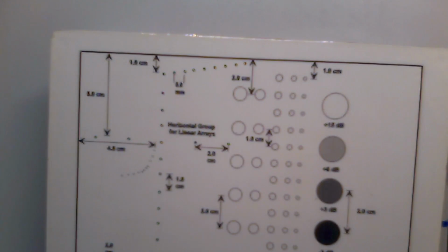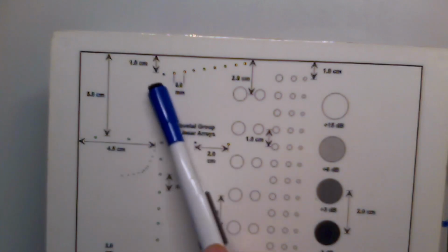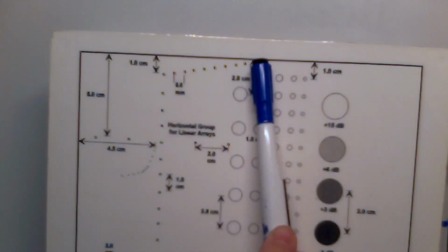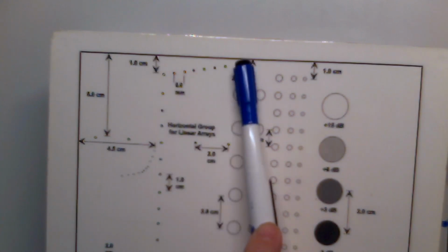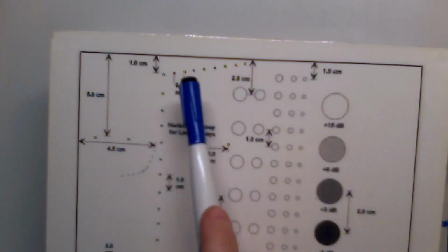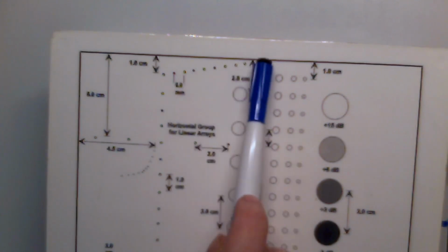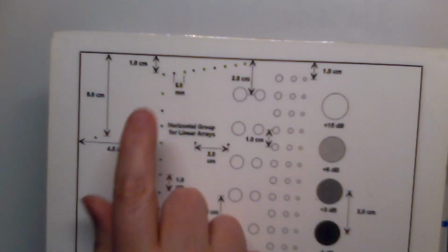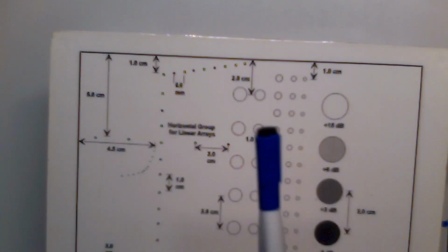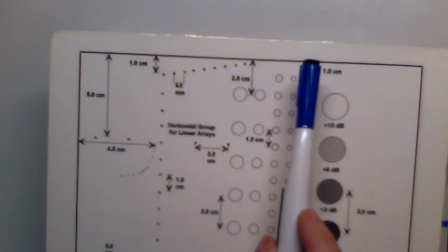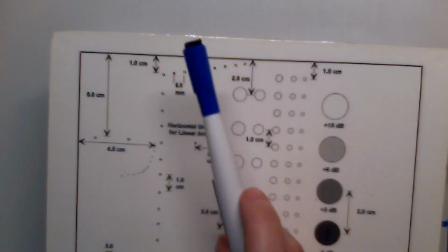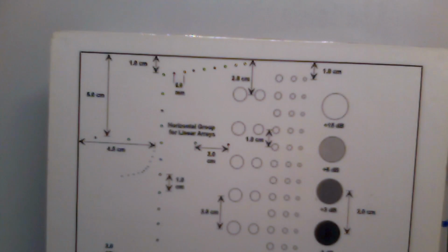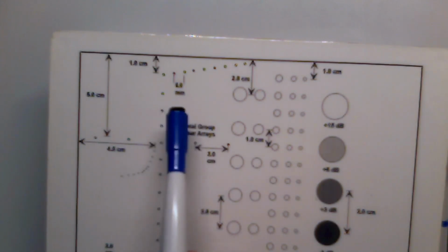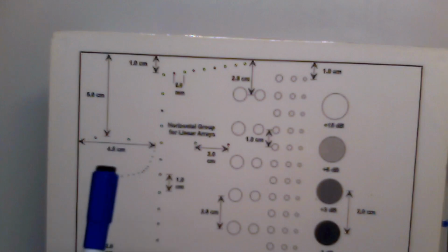Again, we are looking for little pins that are up near the first few centimeters of the phantom. So we're looking at these pins right here. Again, there are 9 displayed here. We want to see when our first one comes in. We can also check the accuracy of the machine in that very near field. We can see from the map on here that these are 5 millimeters apart. So our dead zone becomes deeper as the transducer becomes less effective. So if we have a really, really deep dead zone, it might actually be a transducer malfunction versus something going on with the machine itself.